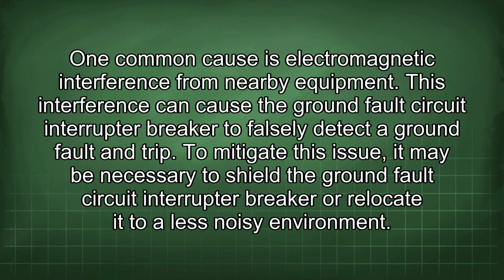One common cause is electromagnetic interference from nearby equipment. This interference can cause the ground fault circuit interrupter breaker to falsely detect a ground fault and trip. To mitigate this issue, it may be necessary to shield the ground fault circuit interrupter breaker or relocate it to a less noisy environment.